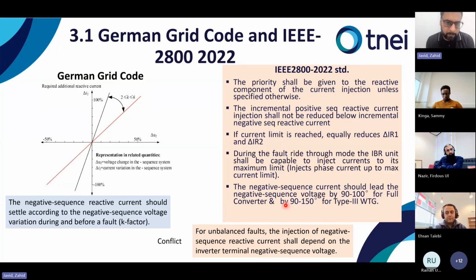But the IEEE 2800 standard has multiple conditions that should be followed. For example, the priority shall be given to the reactive component of the current injection unless specified otherwise, and also the incremental positive sequence current for the balanced fault. The incremental positive sequence current injection shall not be reduced below the incremental negative sequence current. It means if there is capacity remaining or excess, both currents are reduced or increased at the same time. And if the current limits are reached, equally reduce active and reactive current components. And during the fault ride through mode, the IBR unit shall be capable of injecting current to its maximum capacity. And the negative sequence current should lead the negative sequence voltage by 90 to 100 degrees for full converter and 90 to 150 degrees for type 3 wind turbine generators.